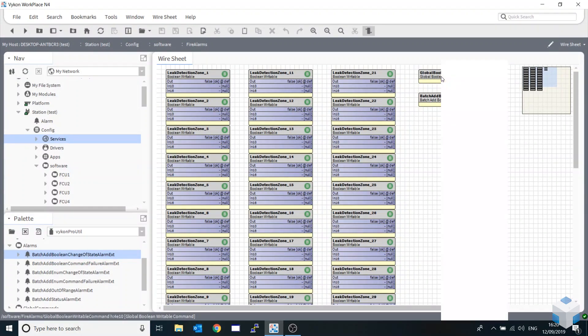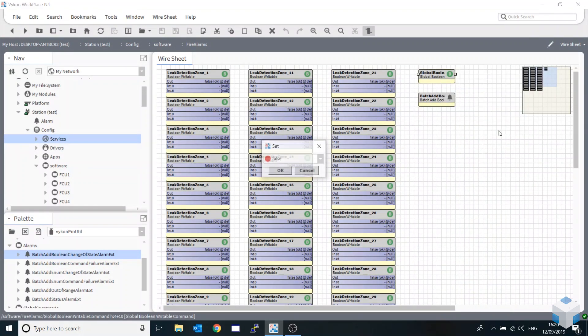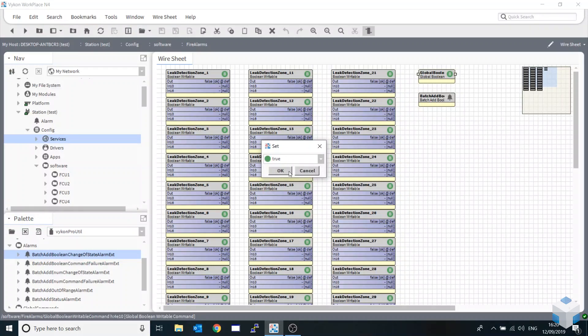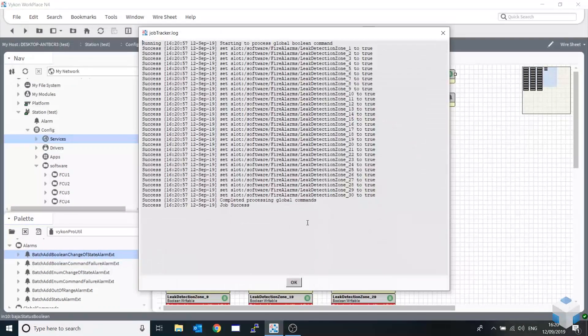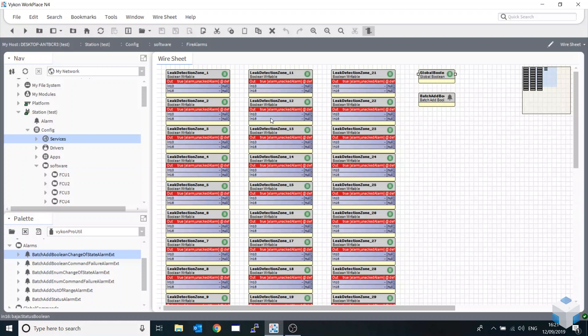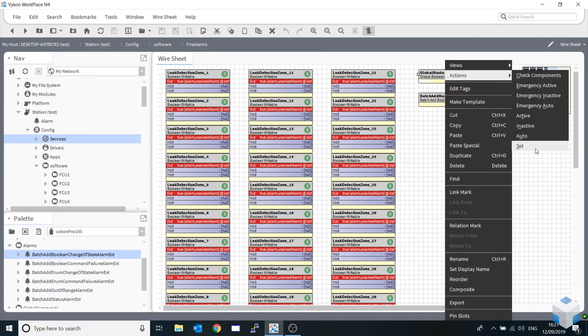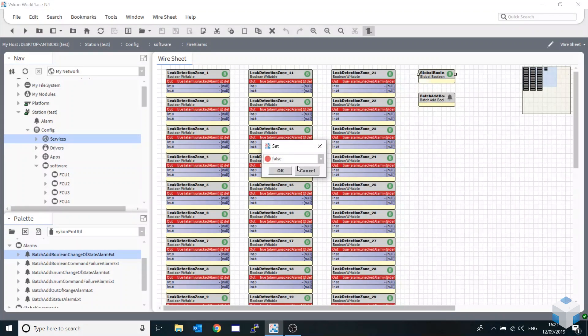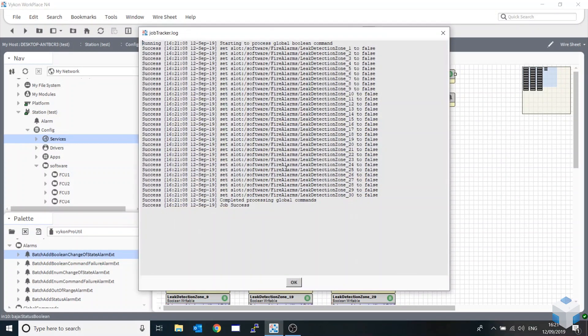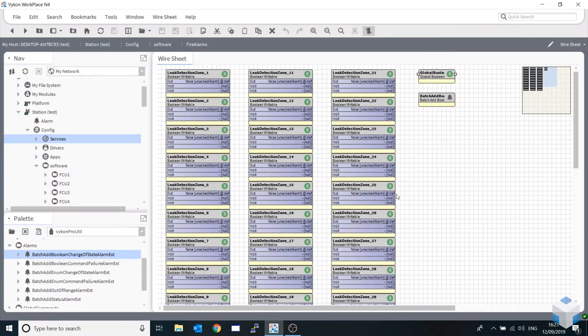Wait for my confirmation, hit OK. I'm going to go into my points now and as you can see it's added a boolean change of state alarm into every single one of my booleans, which is really handy. To test that, we'll be using our global command, hit set and make that go true. Hit the confirmation and as you can see we've got alarms coming through. Very simple, very easy. As you're going to see it really speeds things up quite a lot. I would say if you're going to do this, make sure you back up before you do it just in case you hit something wrong, make a spelling mistake, or actually deploy it to your whole job.